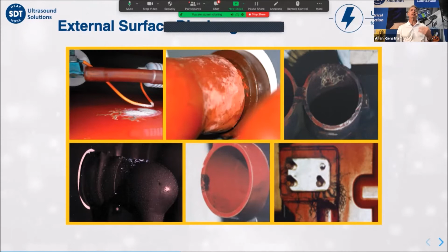Partial discharge has many causes, including, as I said, voids in solid insulation, often caused during manufacturing defects, mechanical breakdown or damage to insulation, sometimes caused by installation or poor workmanship. Design defects such as poor stress control or irregularities, or a combination of factors that are characteristic of assets getting older and just breaking down. Partial discharge emits energy in a number of different ways, producing electromagnetic emissions in the form of radio waves, light waves and heat, acoustic emission in the audible and the ultrasonic ranges, and then again, ozone and nitrous oxide gases, which are corrosive. These sonic emissions are what we focus on with ultrasound, and they enable us to detect, locate, measure, and analyze PD activity so we can identify faults before they develop into failures.